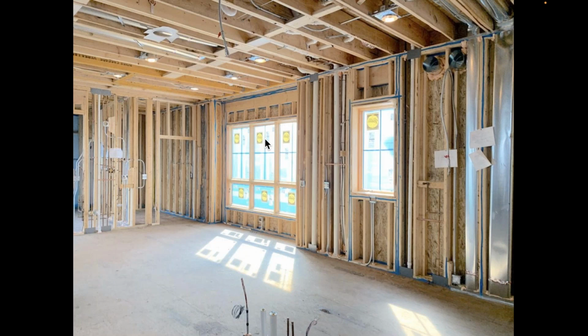And then just paying attention to the details. So for example, here's where the builder really was paying close attention to air sealing. They used this air sealing material around every crack and gap. But what do you see that's wrong with this picture? They didn't pay very close attention to their mechanicals and their electricals. The exterior walls, and you never want to put ductwork in exterior walls. Can you imagine what this would do to your discharge temperature in a winter climate? This cavity is going to be uninsulated unless you happen to have some exterior insulation. So now the discharge temperature coming out of this ductwork, because it's on a cold exterior wall, is going to be much lower than it would have been had this ductwork been placed on an interior wall. Notice all the plumbing. Notice the tremendous amount of mechanical and electrical that we have in these spaces. So there are a lot of simple things that we can do in the building envelope during construction that allow for better heat pump performance in terms of discharge temperatures at the registers, in terms of recovery time, in terms of overall capacity.